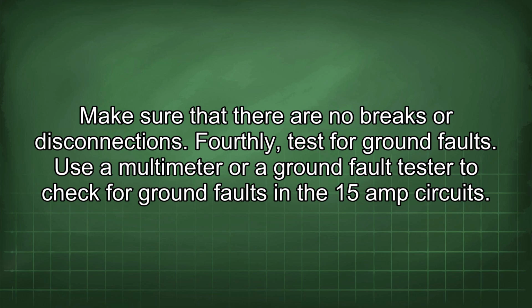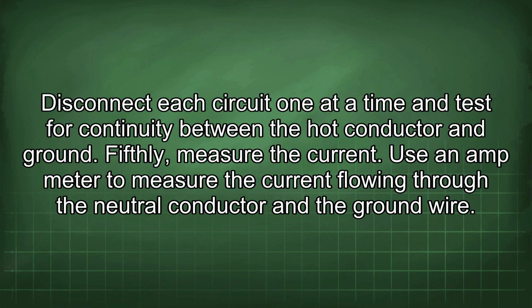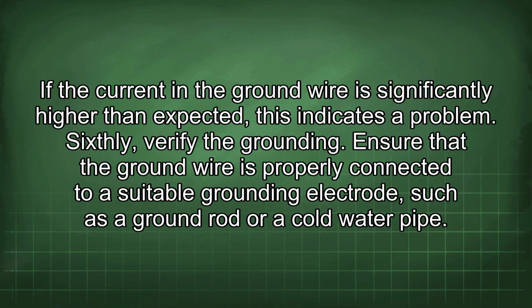Fourthly, test for ground faults. Use a multimeter or ground fault tester to check for ground faults in the 15 amp circuits. Disconnect each circuit one at a time and test for continuity between the hot conductor and ground. Fifthly, measure the current. Use an amp meter to measure the current flowing through the neutral conductor and the ground wire. If the current in the ground wire is significantly higher than expected, this indicates a problem. Sixthly, verify the grounding. Ensure that the ground wire is properly connected to a suitable grounding electrode, such as a ground rod or a cold water pipe.